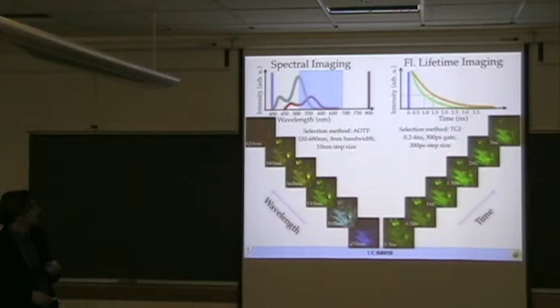The selection method for the spectral imaging is an acousto-optical tunable filter, which is basically an RF frequency-driven, transparent crystal that creates acoustic waves inside, a transient grating that changes the wavelength of propagation through the crystal. So it shows here, in the blue, 2 different structures with 2 different spectra. In the red, these are red blood cells, and the rest is the matrix here. And you can see that they have different spectra, as well as different fluorescence lifetimes, since this is a longer living species and this is a shorter living species.